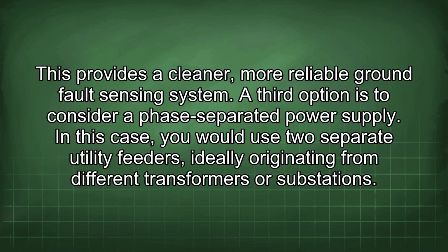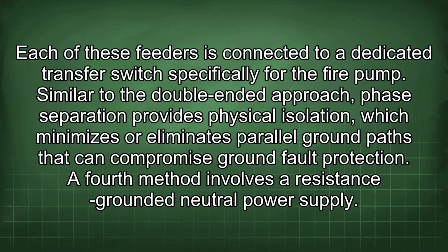A third option is to consider a phase-separated power supply. In this case, you would use two separate utility feeders, ideally originating from different transformers or substations. Each of these feeders is connected to a dedicated transfer switch specifically for the fire pump. Similar to the double-ended approach, phase separation provides physical isolation, which minimizes or eliminates parallel ground paths that can compromise ground fault protection.